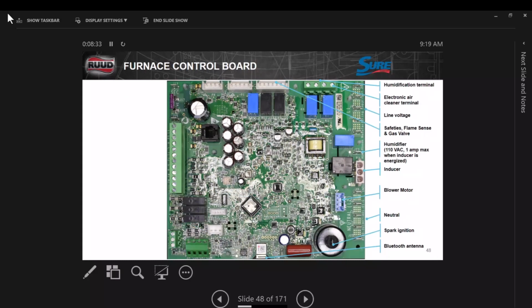Looking at the right side, there's more safeties at the top. This is our flame sensor and gas valve. Humidification terminal. That's humidification, not dehumidification. The next terminal here is our electronic air cleaner. And then right below that's our line voltage terminals. And then as you can see, more safeties go into that plug there where we have our flame sensor gas valve like we talked about. Humidifier, if you're going to use a humidifier, this is where you hook it up, not a dehumidifier. Inducer is going to hook up here. Our blower motor goes there. Neutrals, spark ignition, and Bluetooth antenna, as you can see right there at the bottom.